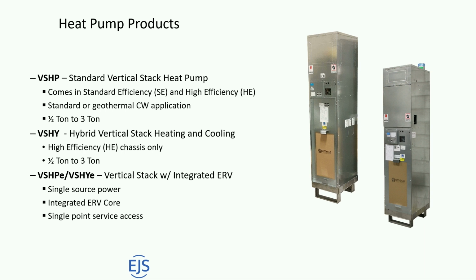The one that everybody knows and loves and typically is using in New York City. We have over 40,000 of these installed in New York City. The VSHP is just your standard compressor in chassis. The compressor actually slides into the cabinet. For service purposes, we can keep 25 of these things, 30 of them down in the basement. When they break, instead of working in their apartment, we can bring that chassis down to somewhere to service it, fix the components, and then it's ready to go into the next apartment. So that's the nice thing about these from a service perspective.